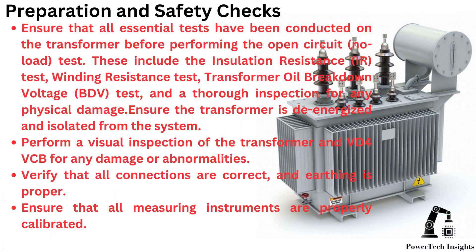Preparation and safety checks. Ensure that all essential tests have been conducted on the transformer before performing the open circuit or no-load test. These include the insulation resistance test, winding resistance test, transformer oil breakdown voltage test, and a thorough inspection for any physical damage. Ensure the transformer is de-energized and isolated from the system. Perform a visual inspection of the transformer and VD4 VCB for any damage or abnormalities. Verify that all connections are correct and earthing is proper. Ensure that all measuring instruments are properly calibrated.